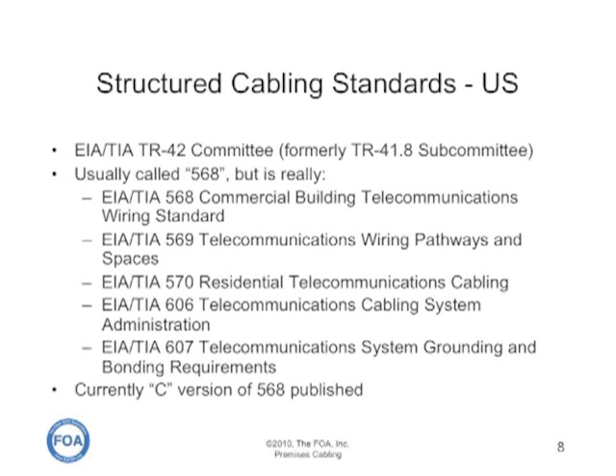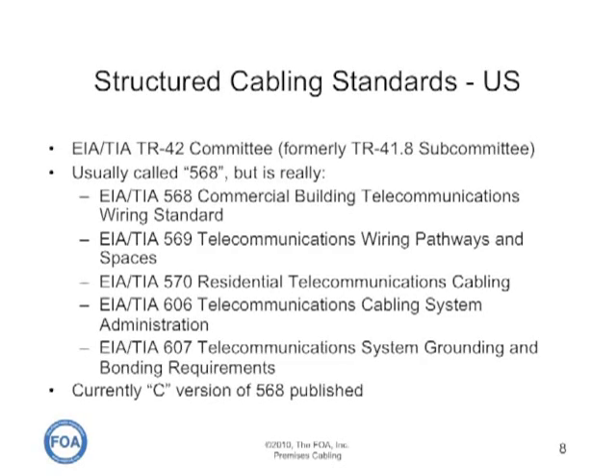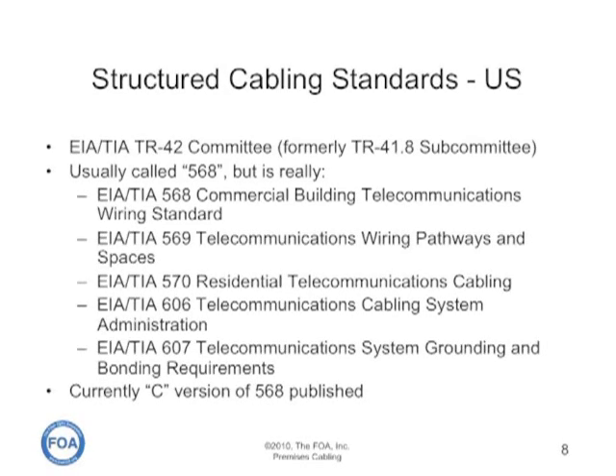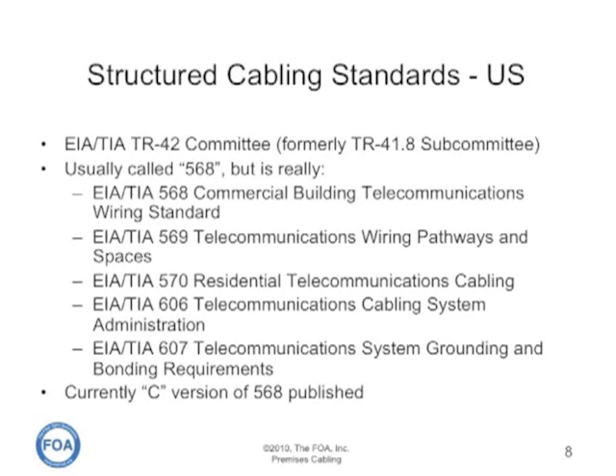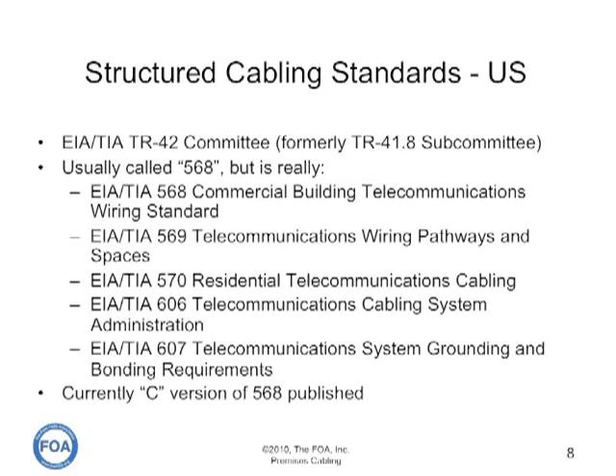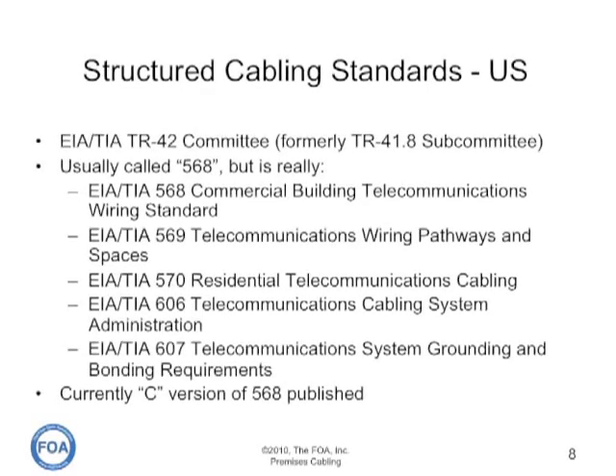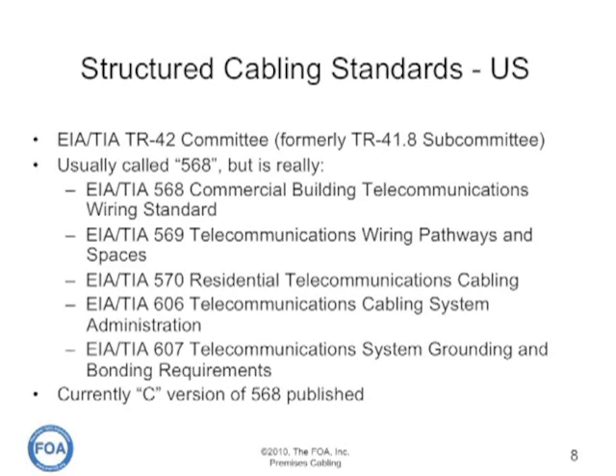In the U.S., structured cabling is based on work by the EIA-TIA TR42 committee. It's usually called the 568 standards, but it's really the 568 standard for building telecommunications, 569 for wiring pathways and spaces, 570 for residential telecommunications, 606 for administration, and 607 for grounding and bonding requirements. At the current time, 568 is in its C revision, but it's being revised continuously, so you really don't know exactly what each standard is in the latest version unless you're a manufacturer attending the standards committees.